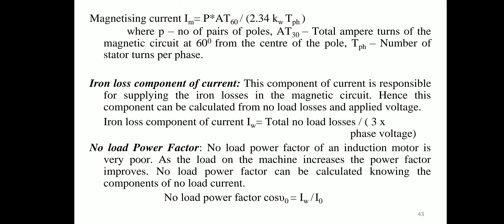Magnetizing current: Im = (p × AT60) / (2.34 × Kw × Tph), where AT60 is the total ampere turns of the magnetic circuit at 60° from the center of the pole, and Tph is the number of stator turns per phase. The iron loss component Iw supplies the iron losses in the magnetic circuit: Iw = total no-load losses / (3 × phase voltage). The no-load power factor of an induction motor is very poor; it improves as load increases.